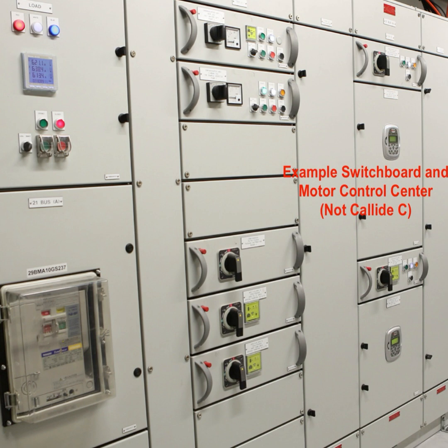On larger, medium, and high voltage circuit breakers in a cabinet arrangement, there is normally one or more pressure relief flaps or doors on the top of each breaker that is specifically designed to open in the event of a rapid buildup of pressure inside the circuit breaker housing that is caused by an electrical arc. The arc itself could be caused by any failure of the circuit breaker itself that led to a fault condition, but it doesn't matter what the reason is. The primary goal is to prevent an uncontrolled explosion.